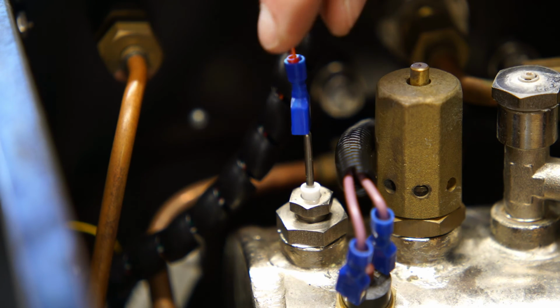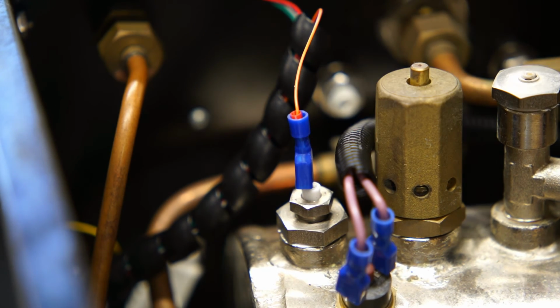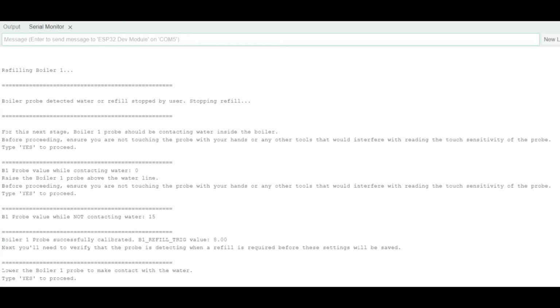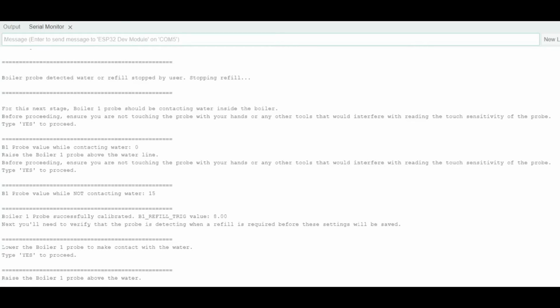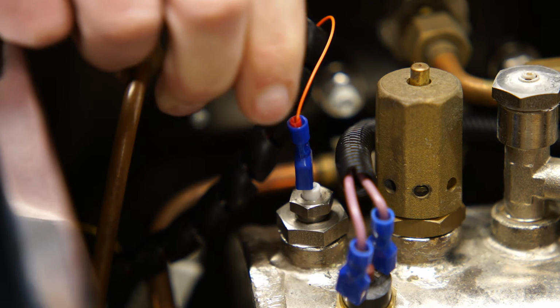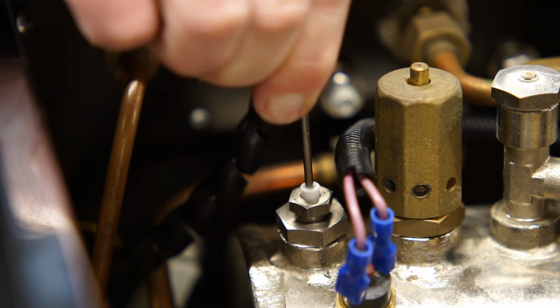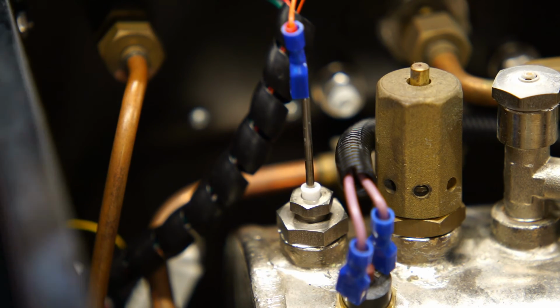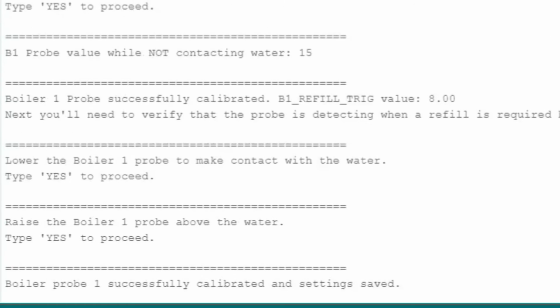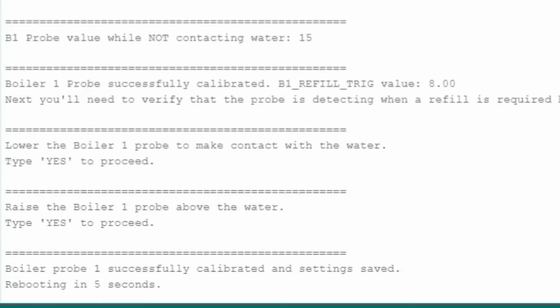To do this, I lower the probe to make contact with the water. Then reply with yes. Then I raise the probe one last time and reply with yes. The calibration wizard confirmed that the calibration was successful and will now save and then reboot.